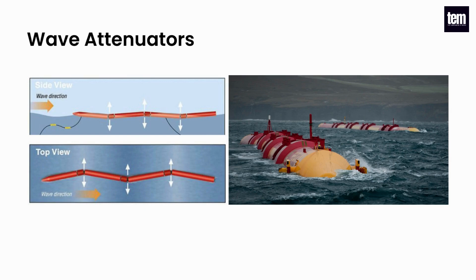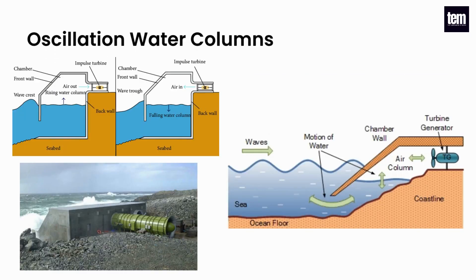Wave attenuators generally have multiple segments connected to one another and are oriented parallel with incoming waves. They use the rise and fall of swells to create a flexing motion that may be converted into rotation or drive hydraulic pumps to generate electricity. Oscillating water columns are a partially submerged closed structure where the upper part, above the water, is filled with air and incoming waves are funneled into the bottom. The waves cause the water column to rise and fall, which causes the air in the top structure to pressurize and depressurize, pushing and pulling air through a connected air turbine at the top, converting the energy into electricity.